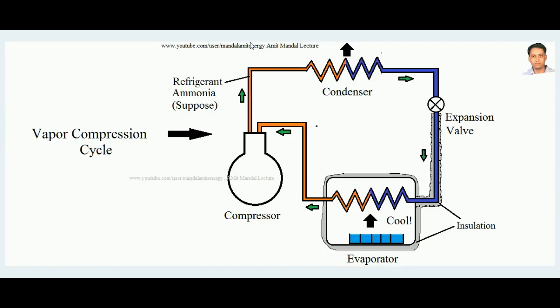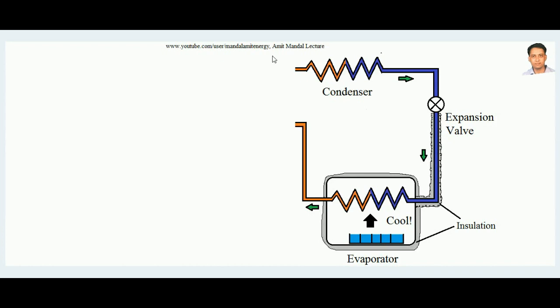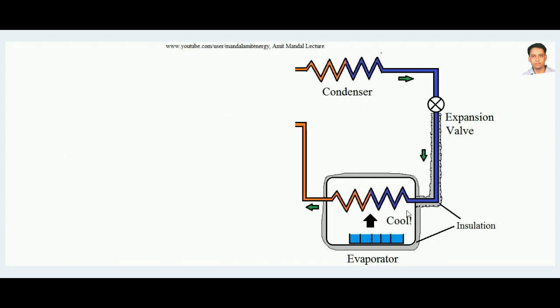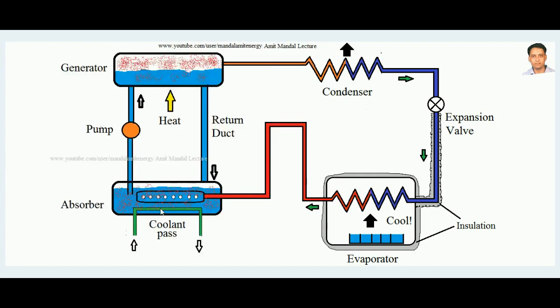From the vapor compression cycle, the compressor part is removed. In the vapor absorption system, aqua ammonia based, instead of the compressor there is a generator-absorber system. In the absorber, ammonia coming out from the evaporator is mixed with cold water. Since ammonia is highly soluble in cold water, it dissolves there. This mixture is called a strong solution.